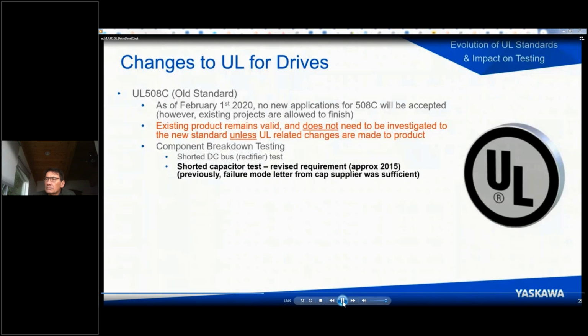And even under UL 508C, there is this thing called component breakdown testing. Okay, and it's very severe kind of testing. One thing we have to do is short the DC bus itself, which is the rectifier, which does cause an explosion by itself. And then also the more severe test is the shorted capacitor test. And previously, UL allowed drive manufacturers to submit a letter from a capacitor supplier to say that this kind of failure was not a failure mode.